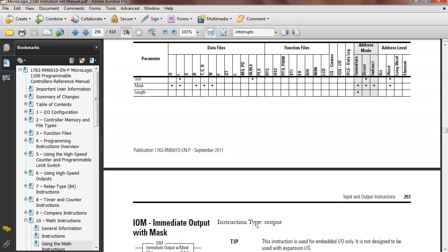If you want something to occur at exactly the same time, no matter what, then you're going to use these. If you want a high priority interrupt where somebody presses an input and that input has to be scanned, then you're going to use an interrupt. You're not going to depend on the scan cycle. You're going to say, that input has got to be detected when I press that button. And that's what you do. Are we okay? Okay, let's go lab, guys.